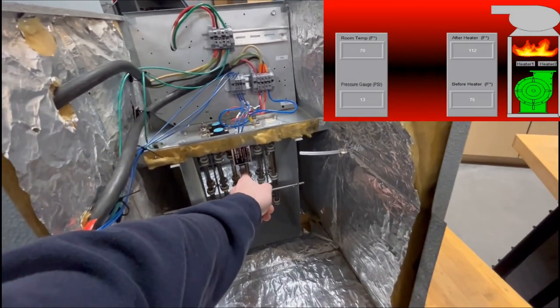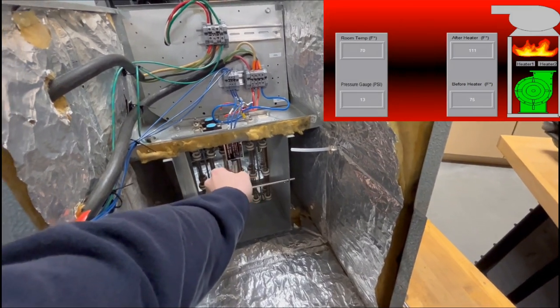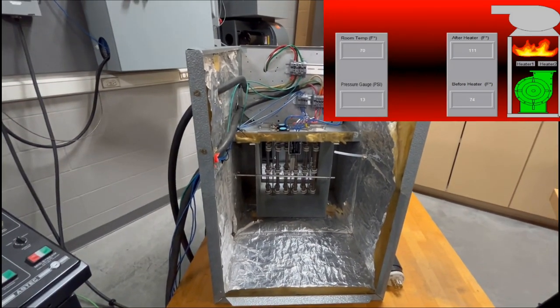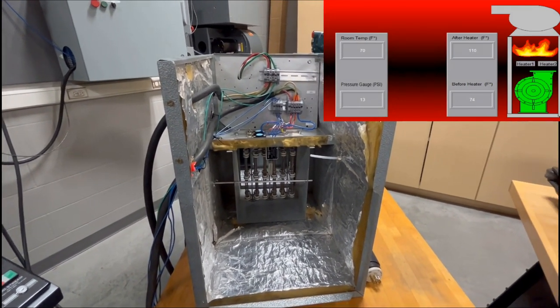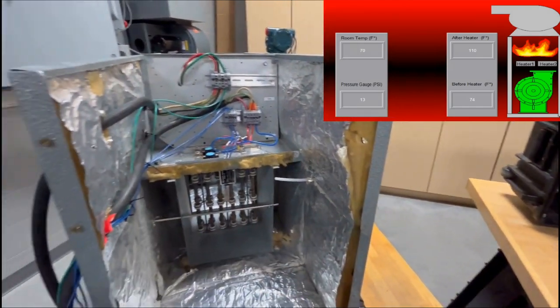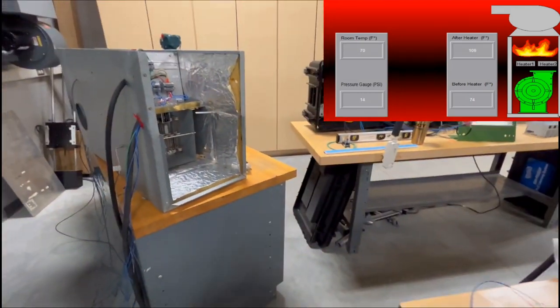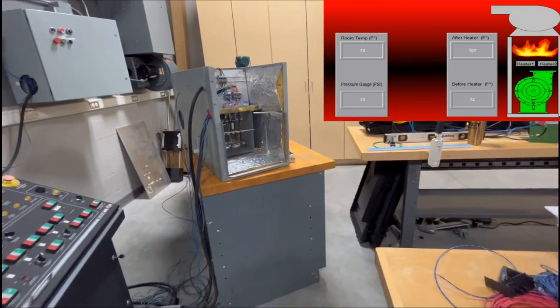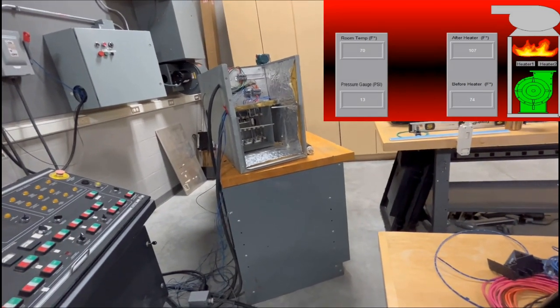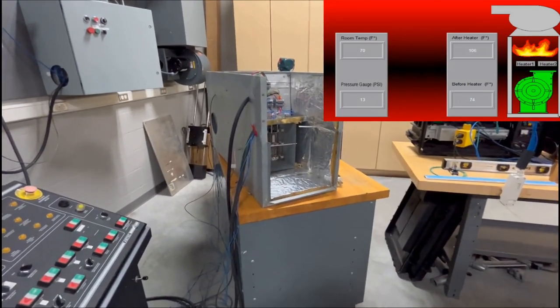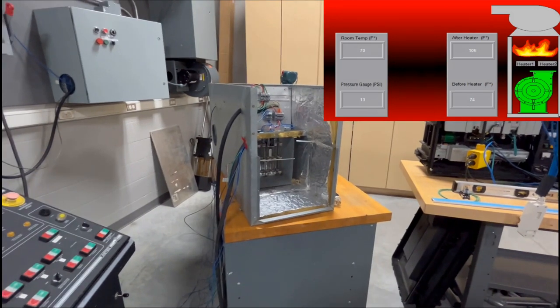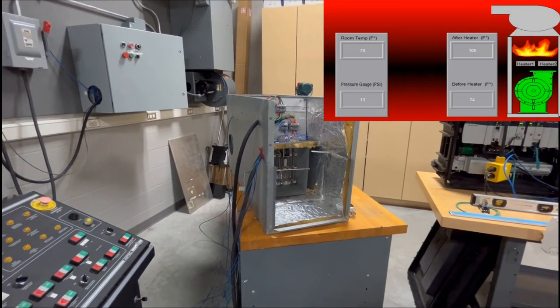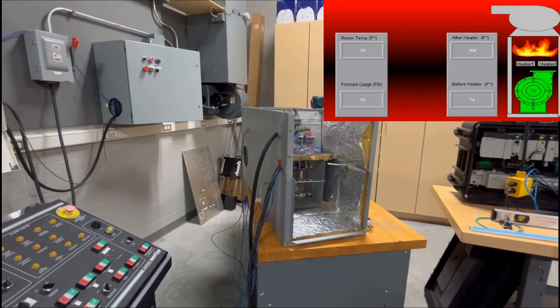We also have this airflow switch that helps me track in my PLC program that we actually do have airflow coming through. And yeah, so this thing's gonna run until that temperature gets within 5 degrees, and it's gonna be running for a while, it looks like. But we'll move on to my CAD and PLC programming.